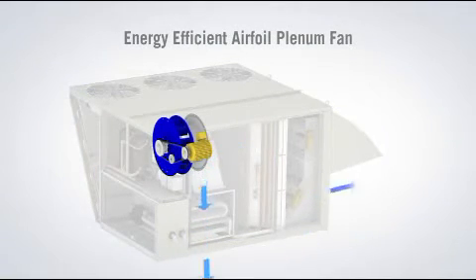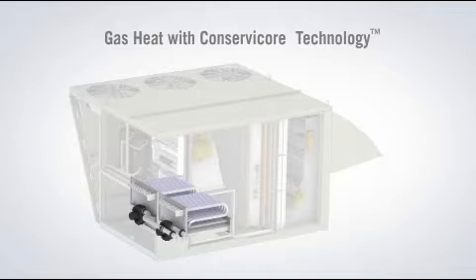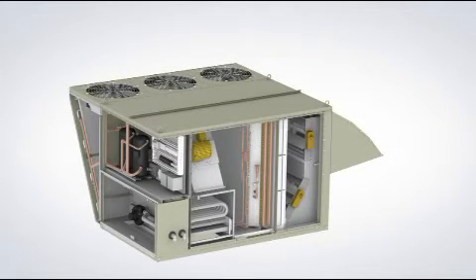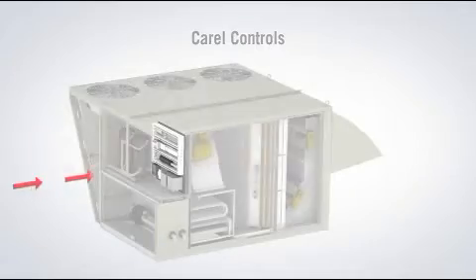All of these components have been designed for maximum performance while maintaining low airside pressure drop. The Quiet Supply Air Fan consists of an energy-efficient, single-inlet, backward-curved airfoil blower assembly. It's designed to slide out for ease of serviceability and includes an automatic belt tensioner. Only Modine can provide an indirect gas-fired heating option with 93% thermal efficiency, thanks to our proven Conservicore Technology. The unit is also available with gas or electric heat with an air temperature rise of up to 100 degrees. Digitally controlled tandem scroll compressors allow cooling output to be turned down to 5% of full rating for maximum efficiency at part load conditions. The Carel Controls can link with the latest control network protocols, letting the unit easily communicate with existing building automation systems.